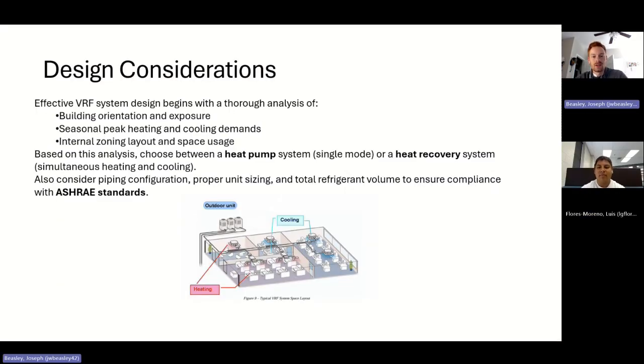So some things that you need to take into design when you're looking at installing a VRF system, or just any HVAC system in general, is your building orientation and exposure. So, you need to look at how the building's situated. The sunny side of the building might need a little bit more cooling in the summer because it's getting the full sunlight compared to the other side of the building. You also need to look at the seasonal demands for heating and cooling. Also, the zoning layout and the space usage, that's where you can really see some of the benefits of VRF, and it can really save you some money when you have a lot of different space loading demands. So in a lot of different rooms, if they're hot and cold.